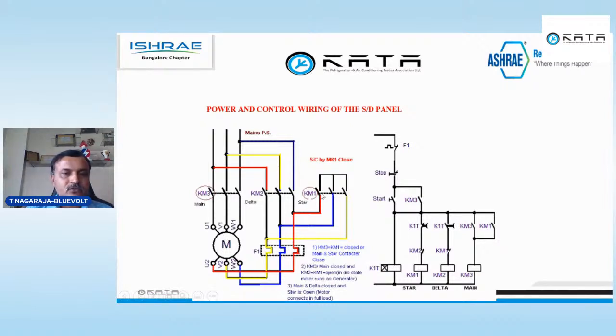Once it starts, after 4 to 6 seconds, this opens and this engages. What will happen? This R will connect to Y. Then automatically you will get 415 volts. It will come to the full speed. All three will be 415, 415, 415. So like this, your star delta contactor changeover will happen.